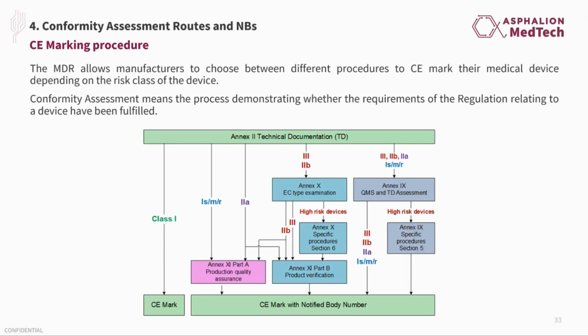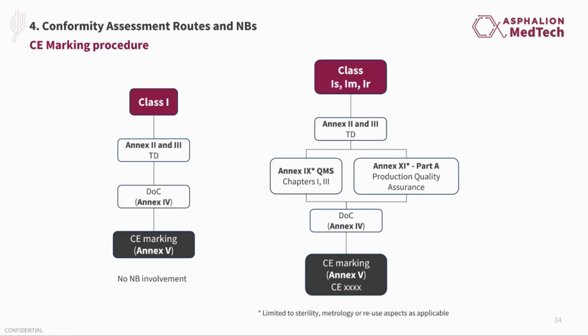Okay, are all routes applicable to all classes of devices? The answer is no, and we can find it in this chart. Let's look at the above chart divided by classes, bearing in mind that depending on the nature of the device, these paths could vary or include more steps. So we have class 1 devices, except sterile devices with a measuring function and reusable surgical instruments. These devices are self-certified by the manufacturer. For higher classes, these are the available conformity assessment routes, being a notified body involved in the process. So all classes must have a declaration of conformity according to Annex 4 and must bear a CE marking according to Annex 5, right?